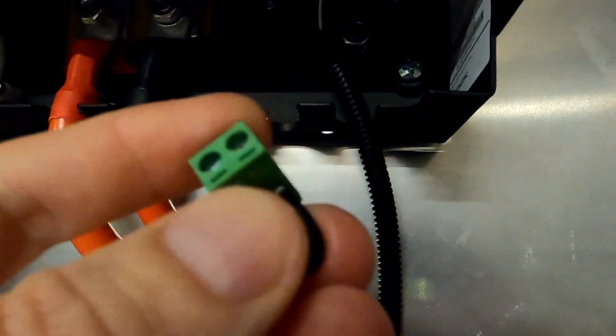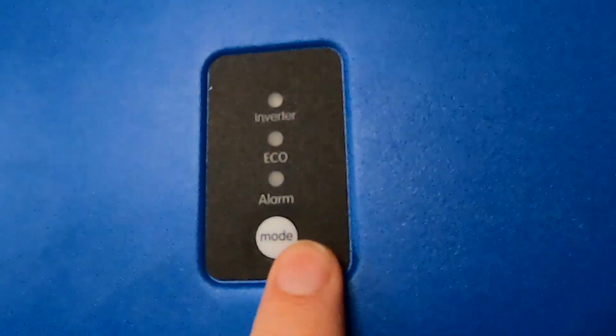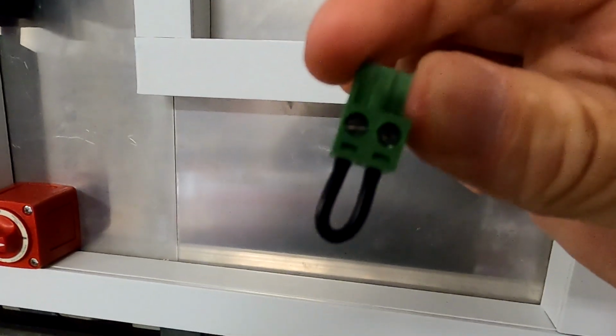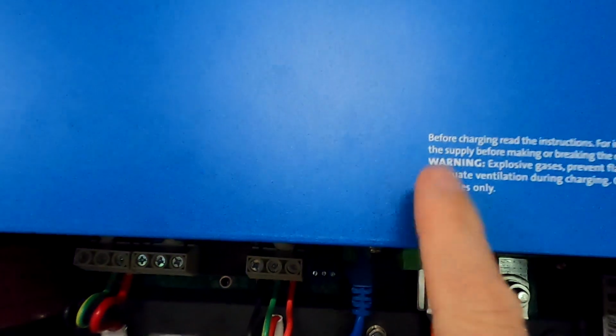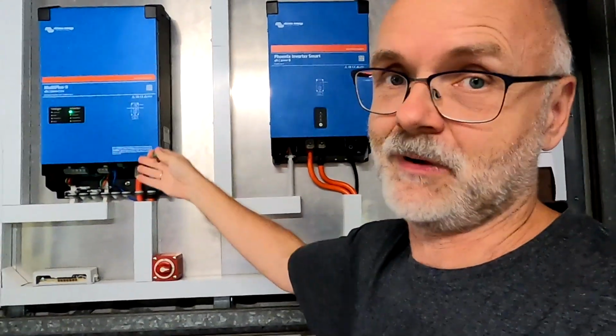And this is actually not hard to do. As you can see, we have this little jumper bridge in here - this is our remote wire. Usually this bridge is installed in the inverter so it turns on by a push on this button. But we can replace this little wire bridge with the contacts of our multifunction relay inside the Multiplus, and then we should be able to set a certain threshold for when we want this one to kick in and support the Multiplus.